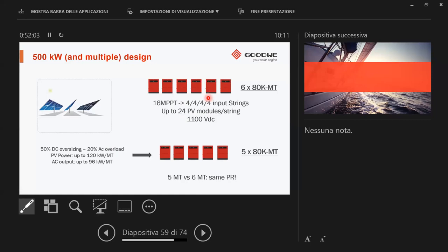The MT series has the characteristic that you can have up to 50% DC oversize, which means with one MT inverter you can drive up to 120 kilowatt PV. If you use six inverters, 80 kilowatt each, nominally you reach 480 kilowatt, but basically you can oversize the DC side even more. And thanks to the capability of AC side overloading up to 20%, this configuration allows you to very easily manage the installation of 500 kilowatt. It's clear that just six inverters is an economic advantage for you.